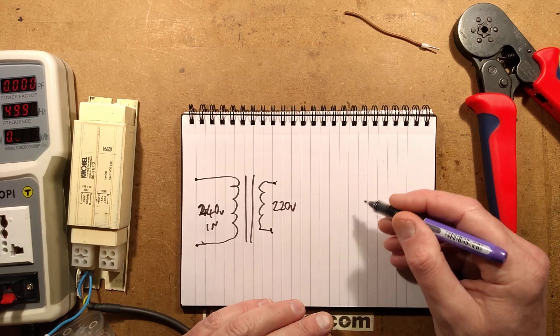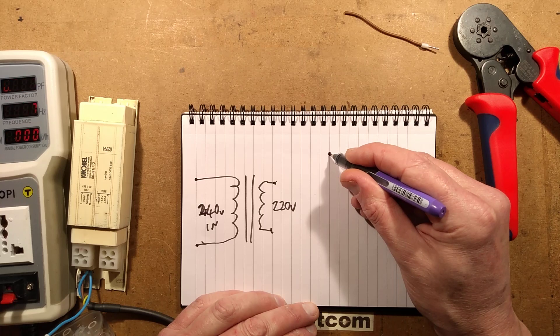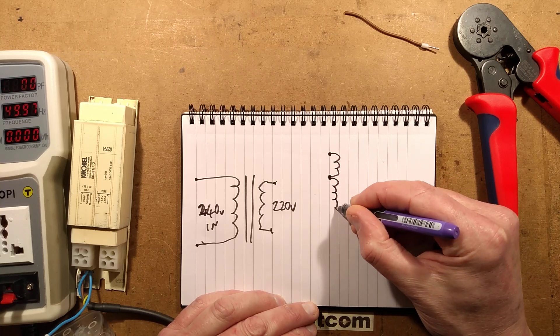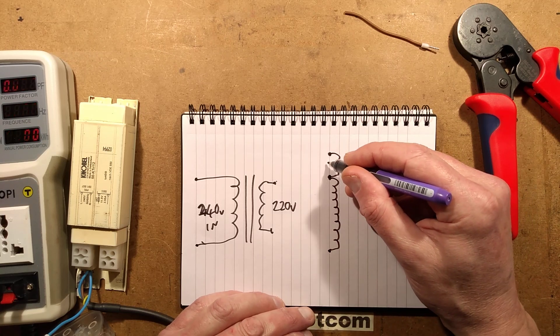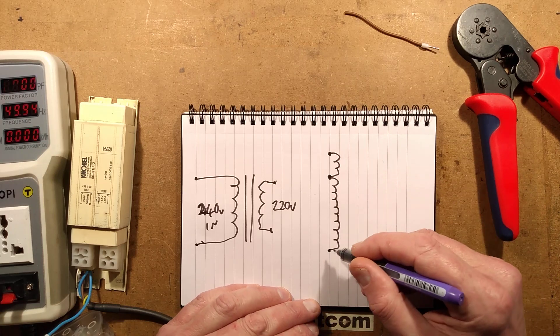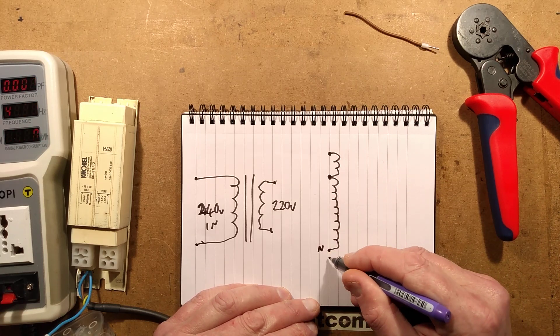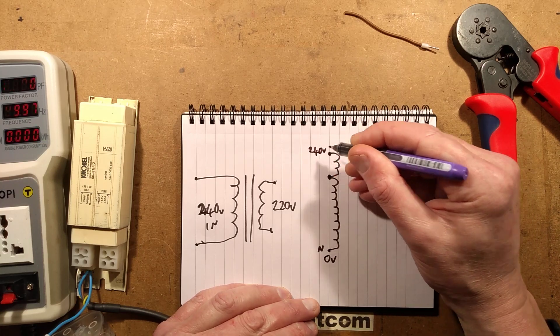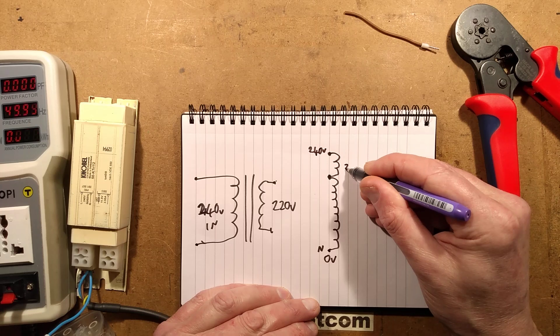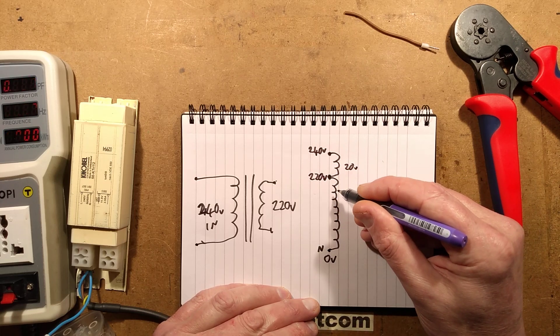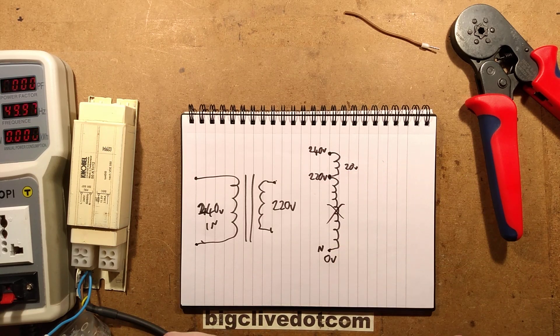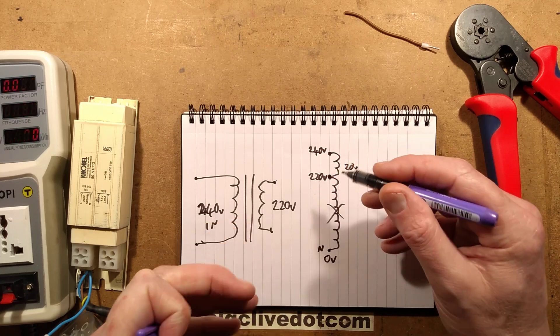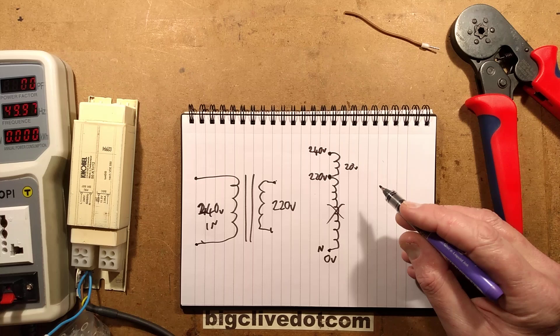That'd be one way of doing it. The other way of doing it would be an auto transformer. One way of doing it is a tapped winding and just a single winding around the whole transformer effectively. That's almost like the secondary, but it's not isolated from the main one. It's just a cheaper way to make them. And you have the neutral connect down here or zero volts as it's often referred to. You have the 240 volt supply connected here and you've got a tap at 20 volts. So you get 220 volts out of this point.